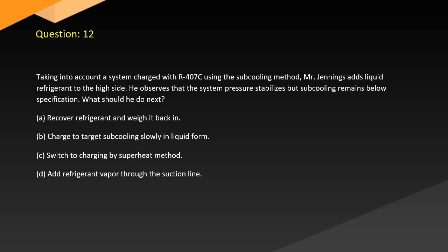Question 12. Taking into account a system charged with R407C using the subcooling method, Mr. Jennings adds liquid refrigerant to the high side. He observes that the system pressure stabilizes, but subcooling remains below specification. What should he do next? A. Recover refrigerant and weigh it back in. B. Charge to target subcooling slowly in liquid form. C. Switch to charging by superheat method. D. Add refrigerant vapor through the suction line.